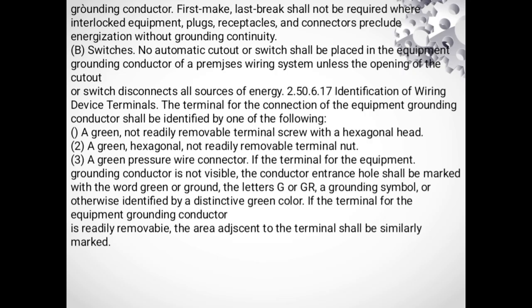Grounding conductor first make, last break shall not be required where interlocked equipment, plugs, receptacles, and connectors preclude energization without continuity. B. Switches. No automatic cutout or switch shall be placed in an equipment grounding conductor of a premises wiring system unless the opening of the cutout or switch disconnects all sources of energy.